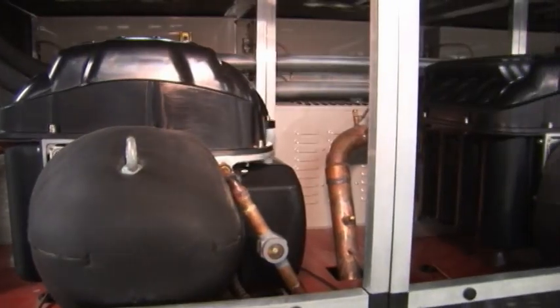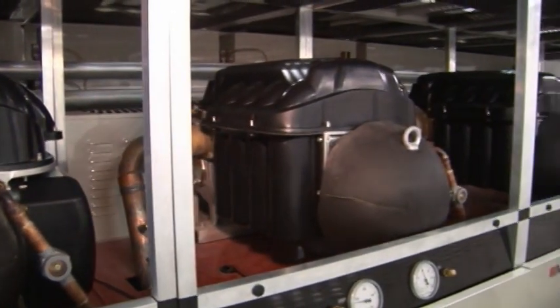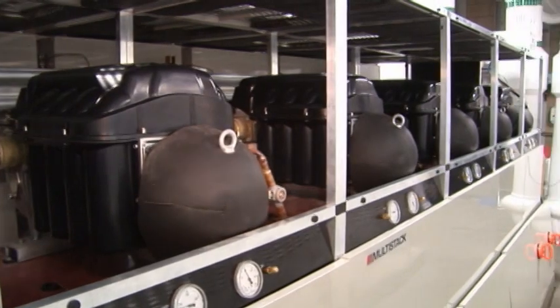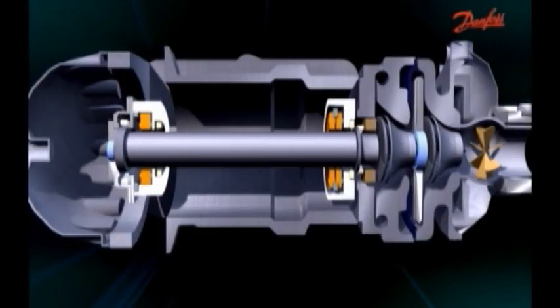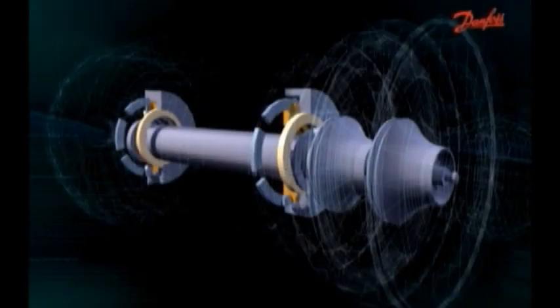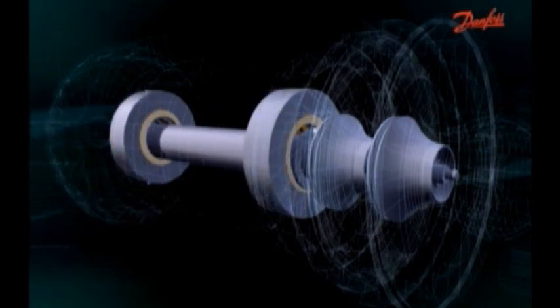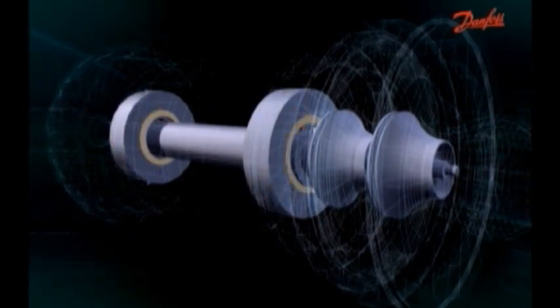We decided to go with the Turbocor multi-stack compressor due to the fact that we were looking for some redundancy, energy efficiency. Environmentally, we were looking at oilless compressors, and I think what Turbocor had to offer was ideal. Turbocor's variable frequency drive design allows its compressors to work at variable speeds. A variable speed compressor allows you to operate at its most efficient point given any set of conditions. By only having one moving component, there's reduced maintenance cost and reduced operating costs as well.